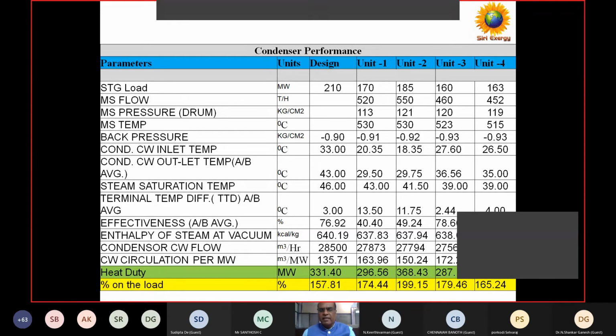But the problem is they said they cannot run with a single pump, so they operate with 2 pumps. We told them maybe you can go for throttling, but because these are very big pumps, they don't want to take any risk of throttling. Otherwise they can go for variable speed drives, but particularly HT drives, nobody wants to go for it.